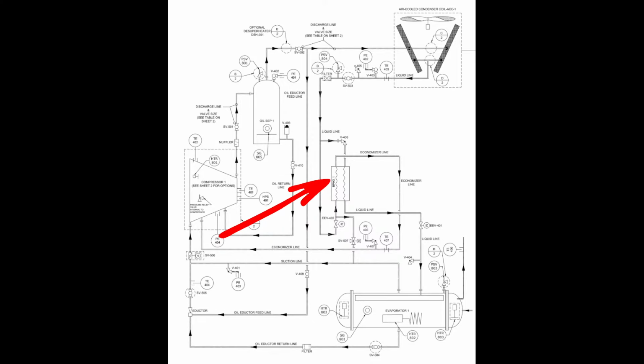Why is, let me see the question here. Why the oil sump tank freeze? Yes, so we do have oil separators on the YVAAs. Yes, so most of these air-cooled screws or just most screw machines are going to have an oil separator, air-cooled, water-cooled. The only machine that has a built-in is the Hanbell compressor. So the Hanbell still has an oil separator, but it is built into the compressor housing for the Hanbell series. Hanbell's not the only one that has a built-in separator. It's just one of the more common ones we'll see in the field. And then your question about the oil sump tank freezing up or condensating, I will circle back to that in just a minute.